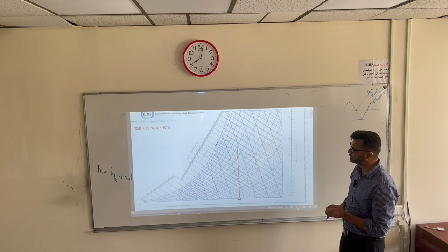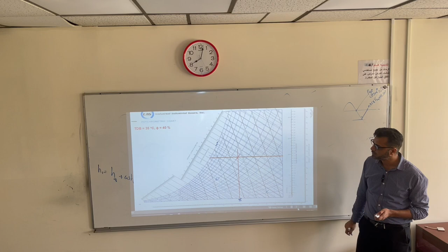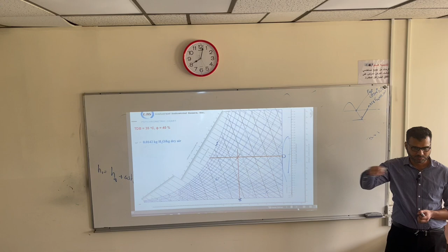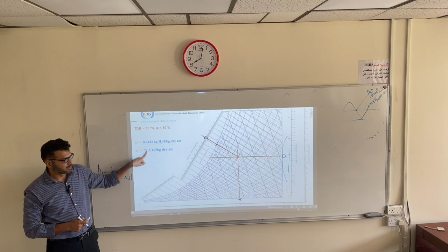So we need to find the specific humidity. Draw a horizontal line to read specific humidity here. Its units are also written, kilograms per kilogram of dry air. So specific humidity is horizontal. This is wet bulb or enthalpy. Both are almost parallel, so you can read enthalpy or wet bulb enthalpy. These are the enthalpy lines. So read enthalpy, 71.5 per kilogram of dry air. Enthalpy of air per kilogram of dry air.